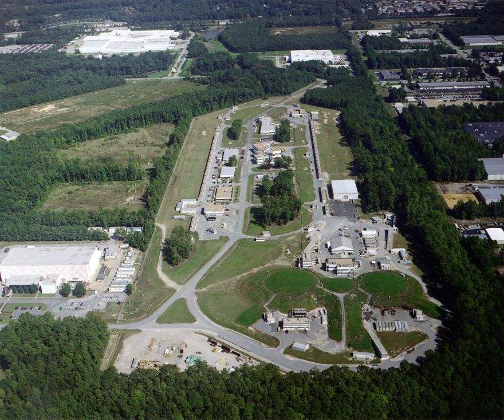Another is Jefferson Lab's use of superconducting radio frequency (SRF) technology, which uses liquid helium to cool niobium to approximately 4 K (-452.5 degrees Fahrenheit), removing electrical resistance and allowing the most efficient transfer of energy to an electron. To achieve this, Jefferson Lab houses the world's largest liquid helium refrigerator, and it was one of the first large-scale implementations of SRF technology. The accelerator is built 8 meters below the Earth's surface, or approximately 25 feet, and the walls of the accelerator tunnels are 2 feet thick.